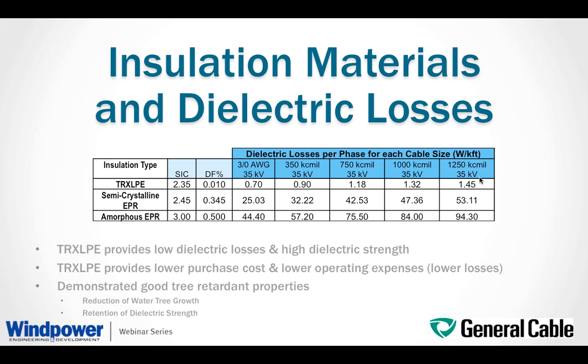semi-crystalline EPR. In this table, you can easily see the comparison of the EPR and the dissipation factor characteristic and associated dielectric losses of each type of insulation. The EPR versus TRXLPE comparison demonstrates well that TRXLPE insulation has much lower losses than any EPR. TRXLPE typically provides a lower purchase cost and lower operating expense than EPR. Again, it is worth noting that both materials have good tree retardant properties, which will ensure reduction of water tree growth within the insulation and retention of the dielectric strength of the insulation material.